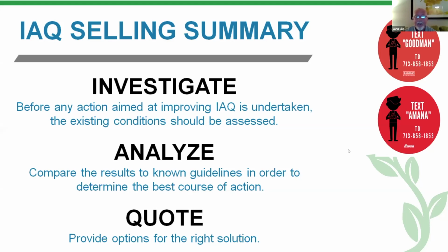But you have all these numbers, and you need to go: if you have high particulates in your house, a UV light is not going to be the answer. So we need to make sure we are looking at what the data is telling us and follow where it leads, our filtration. Maybe we want to look at our building pressures and tie those two together, because all the filtration in the world is great, but if our infiltration is greater, it's going to be a wash. So it's important to really look at the data.